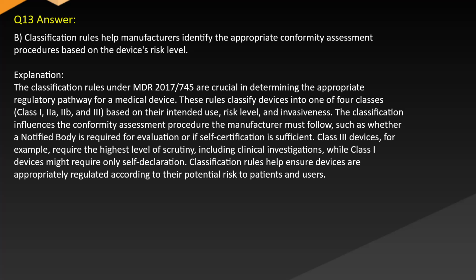Explanation. The classification rules under MDR 2017-745 are crucial in determining the appropriate regulatory pathway for a medical device. These rules classify devices into one of four classes, Class I, IIa, IIb, and III, based on their intended use, risk level, and invasiveness. The classification influences the conformity assessment procedure the manufacturer must follow, such as whether a notified body is required for evaluation or if self-certification is sufficient. Class III devices, for example, require the highest level of scrutiny, including clinical investigations, while Class I devices might require only self-declaration. Classification rules help ensure devices are regulated according to their potential risk to patients and users.